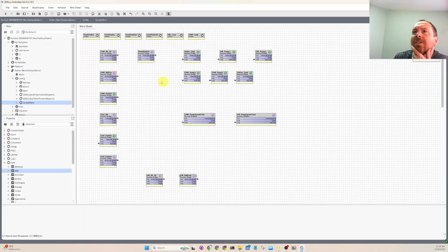Well, let's see if it'll start the boiler. So let's simulate the outside air temperature going cold enough to start a boiler, and the chiller goes off and heat comes on. Okay, that's good. All right, and still, the pumping logic, or the PID, didn't work for the boiler.